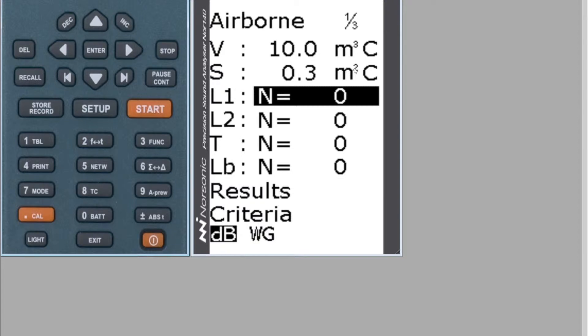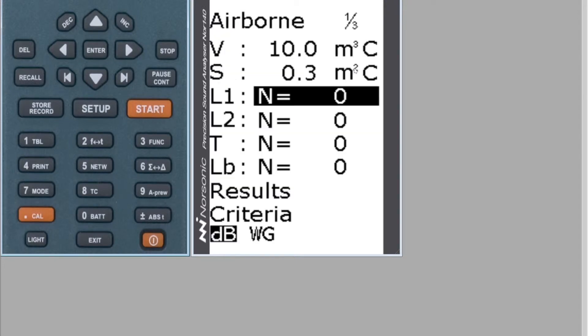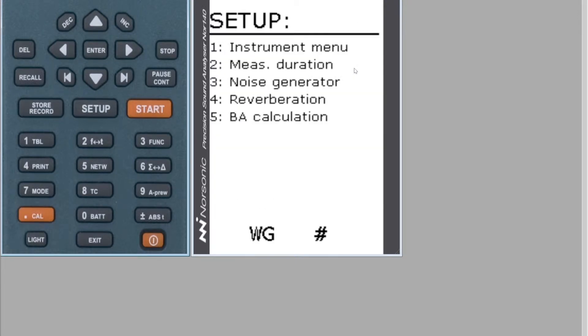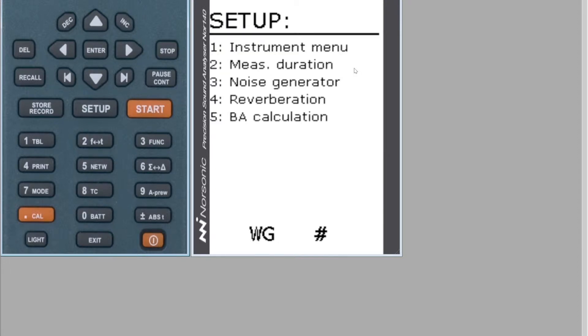Before we go any further, let's go into Setup. To come back out of Setup, press the Enter key. Go to Measurement Duration, which is number two, and then change this duration to whichever method you're using. I'm going to use the six-second fixed point measurements, so type in 06 — you'll see there's an E at the bottom which means press Enter — and if you hit Enter again it will bring you back to the Setup menu.